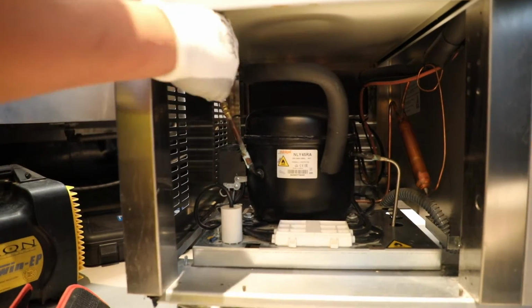Talk me through that reclaiming the gas process. Is that cost effective? How difficult is it to do, and how do you guarantee that it gets done? Yep, so technicians do need to be trained to do it, and you do have to invest in some equipment. So you need recovery units and recovery cylinders. There would be one cylinder for 404, one cylinder for 134. They can't be mixed, so it can't be recycled, it can't be purified if those are mixed in the same cylinder.